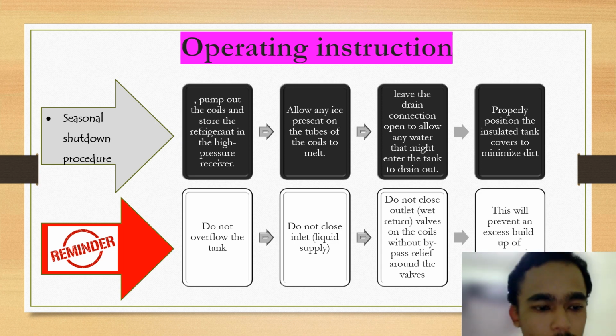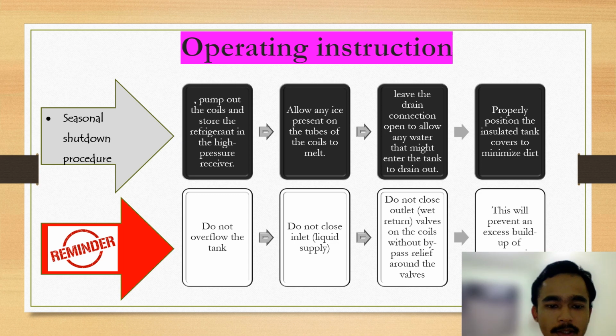And for safety reminder, do not overflow the tank, do not close the inlet which is for the liquid supply, and do not close the outlet or the wet return valve on the coils without bypassing the relief around the valve, because this will prevent an excess build-up of pressure in the coils.